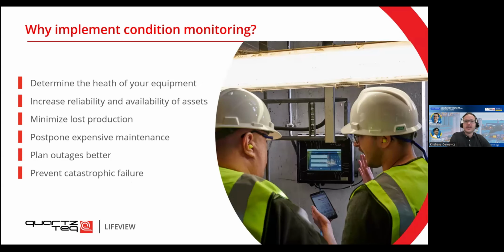So here, I put down the key benefits of implementing condition monitoring on your machines. So first of all, like I said, it's determining what the health of the machine is at this particular moment. We can also increase the reliability and availability of the assets, because if the machine is healthy, there's a very low chance that something bad will happen and there's going to be a failure. We also minimize lost production time in that sense. And like I said, we can postpone expensive maintenance. If the machine is in a very good condition, maybe the maintenance can be pushed to a later time. This also allows us to plan outages better. If we know that multiple parts of the machine are approaching the maintenance time, maybe we can schedule it earlier or schedule it at the same time that we do the repairs.